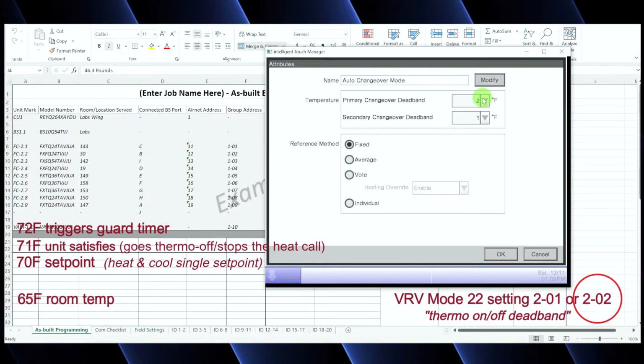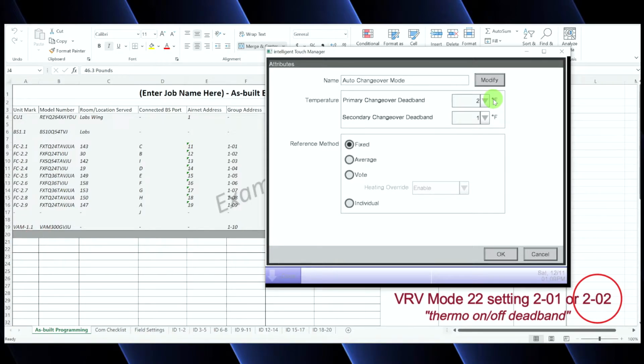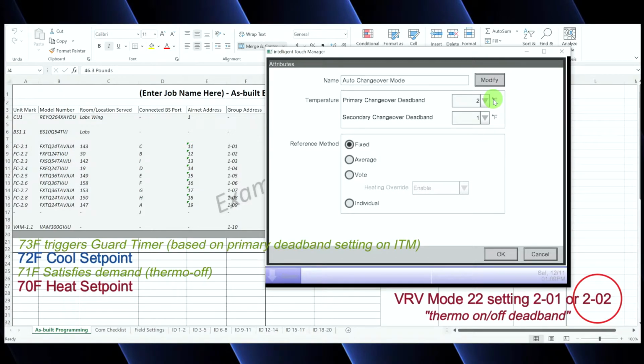Now, most of the time, we like to use what's called dual set point. Dual set point means I'm going to heat to 70 and I'm going to cool to something like, I don't know, 72. There's a buffer in between 70 and 72. So when my unit satisfies at 71 in the heat mode, technically it still needs to get at least to 73 degrees before it can switch over. In that case, you can change your primary deadband to 1, because when it satisfies at 71 degrees, it's not going to immediately switch modes. The room temperature has to get to the cooling set point, which is 72 in this example, then has to get 1 degree past that. That 1 degree past that is right here. 1 degree past the cooling set point will trigger the guard timer, which we set for 30 minutes.